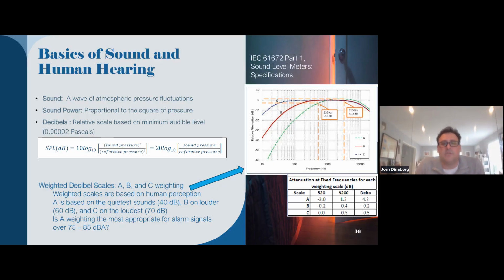So one of the reasons this really comes into question is the A rating is based on the limits of hearing. So what humans hear at really, really low levels, about 40 decibels, the quietest sounds that they're able to pick up, this is where that A rating impacts as a function of frequency. The B and C ratings are actually meant for much louder signals up to 60, 70 decibels. And they weight those low frequencies with a stronger component than the A rating. So there's a question here about if the A rating is really appropriate for alarm signals, which are based at 70 to 75 to 80 decibels, when the A rating is really meant for about 40 decibels. So maybe we're really punishing this 520 hertz signal, making it have that same A rating, but maybe that's why it's more effective at the same A rating, because we're essentially punishing it and requiring more power.